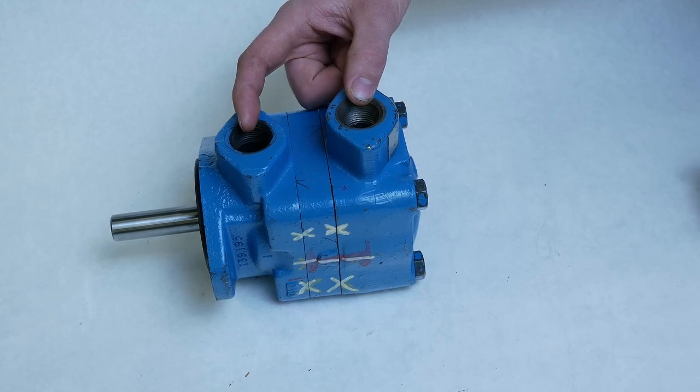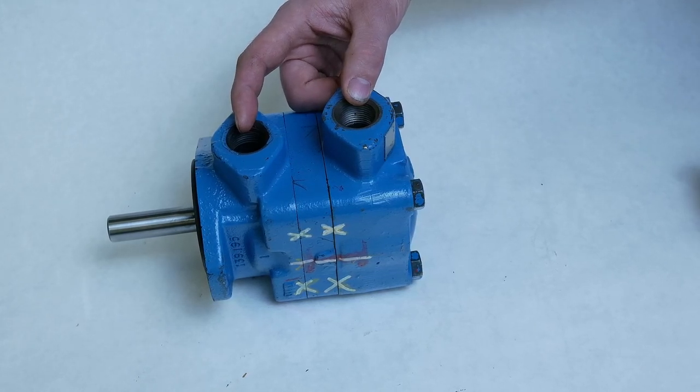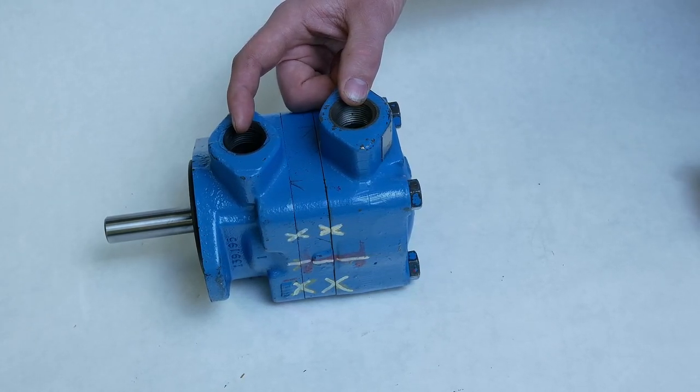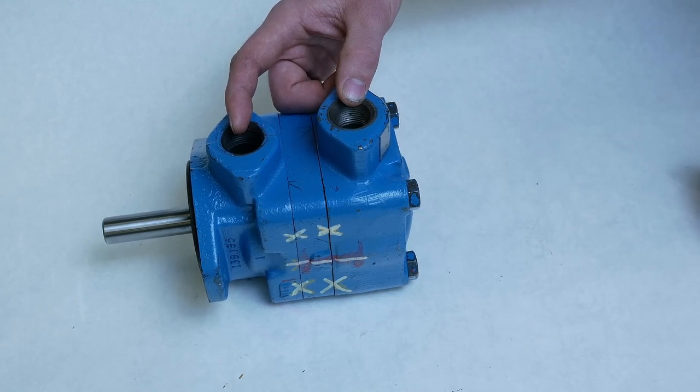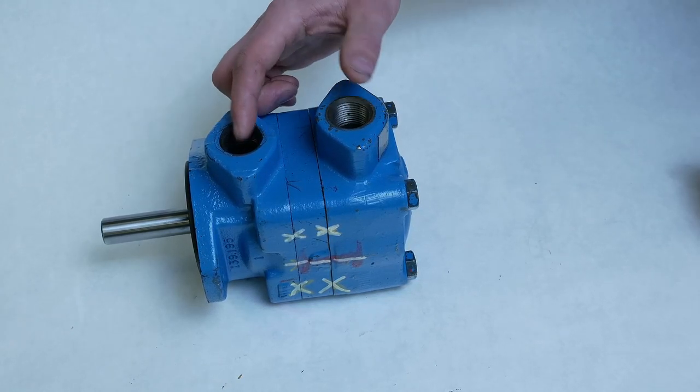Typically on a vane pump, the inlet would be larger than the outlet. But on a vane motor, because they're most commonly bi-directional and reversible, they'll be of equal size.